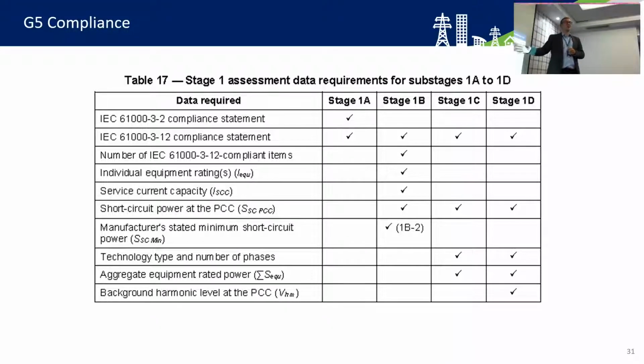This was problematic equipment. We've got this double-edged sword - we really want to promote low carbon technology and decarbonisation, but we've also still got to adhere to certain standards. If somebody phoned us up tomorrow and said their lights keep popping and electronic equipment keeps failing, and we went and measured the background levels and there was a 10% issue, we'd have a problem. We'd have to resolve that, and that might mean hundreds of thousands of pounds of reinforcement work. So this is the double-edged sword - we want to promote this equipment, but we also need to protect everybody's supply.